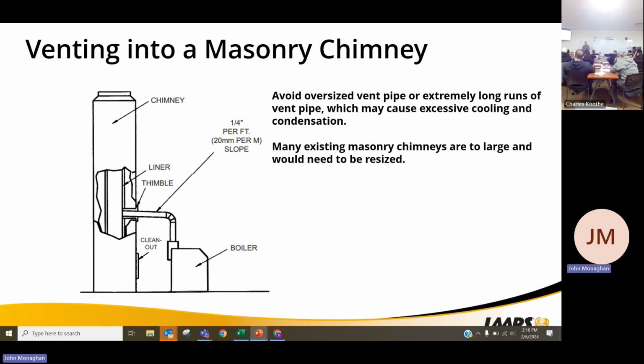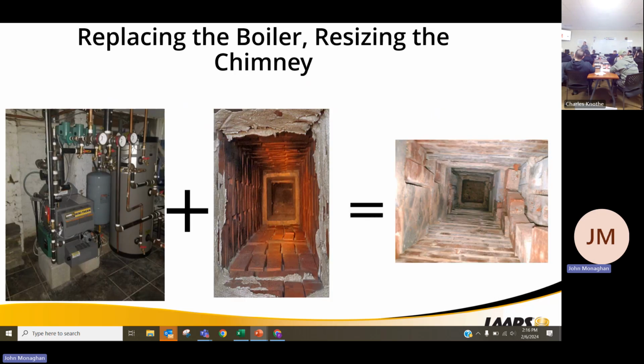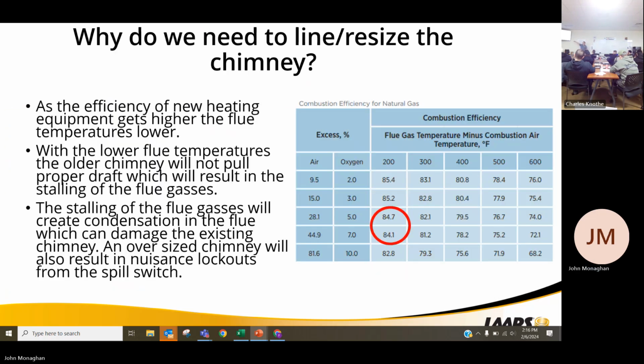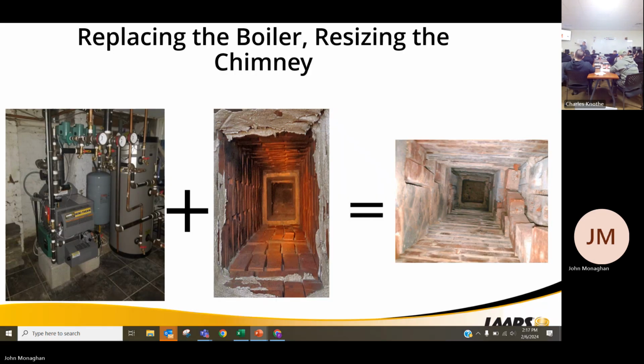If we look at some of the products that we're taking out, those flue temperatures are much higher than our new products. For the most part, on a cast iron or mid-efficiency product, we're all floating around 84% efficient. At 84% efficient, our flue gas temperatures are 200-300 degrees, much lower. If we're condensing in our chimney, I got to flip these slides around. We'll put in a nice new mini therm. That chimney may look nice and square, and everything will be good to go.